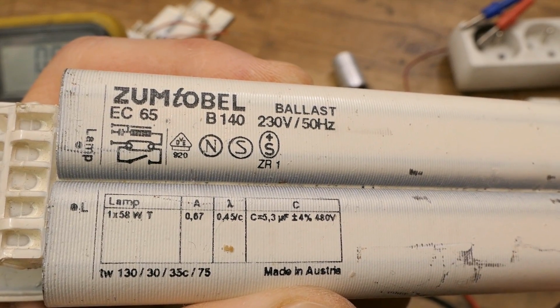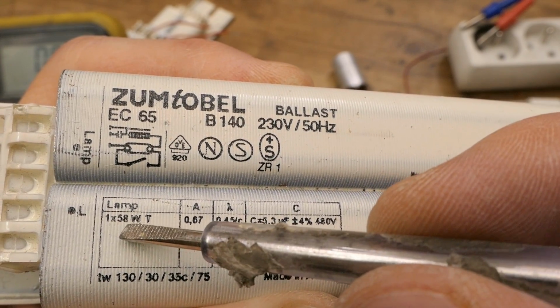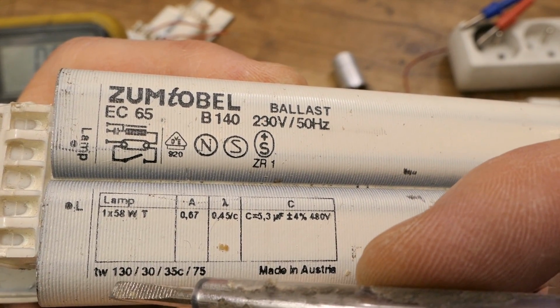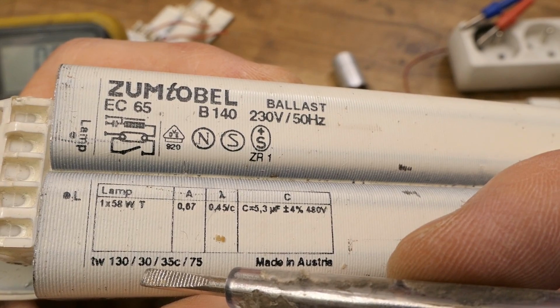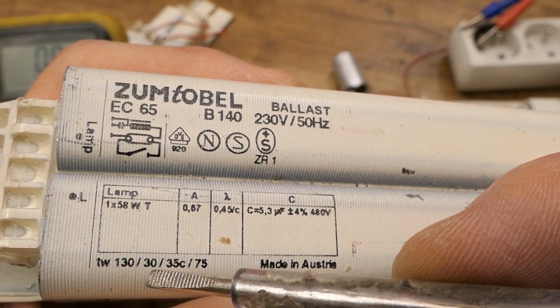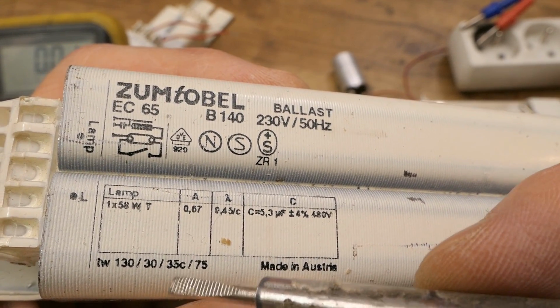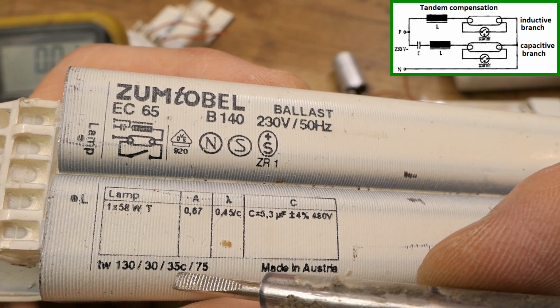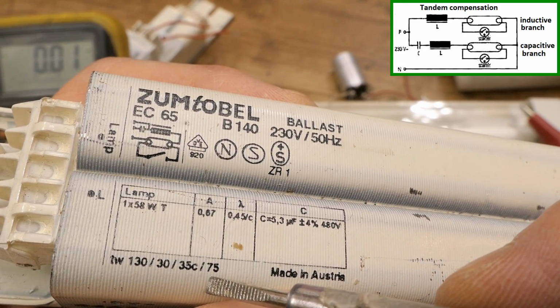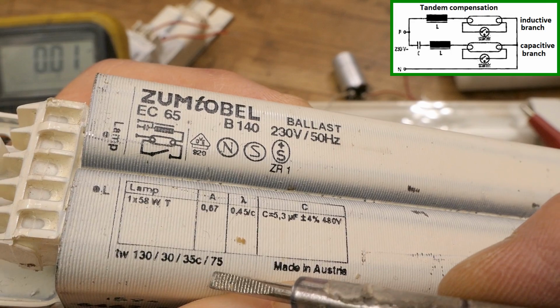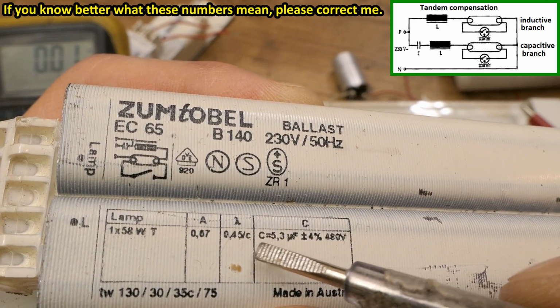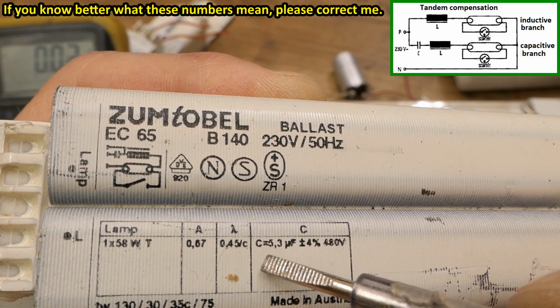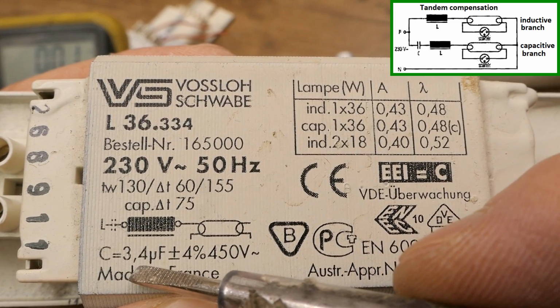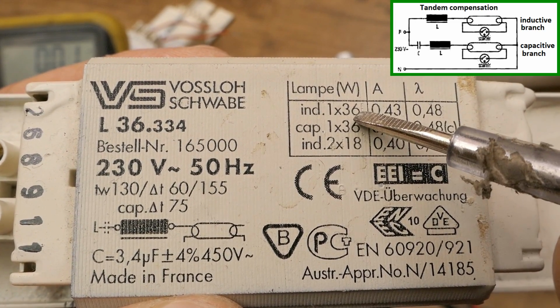To make it even more confusing, this is a 58 watt tube inductor, 130 degrees Celsius, 30 degrees Celsius temperature rise for normal operation, and 35 degrees Celsius temperature rise for the capacitive branch. And 75 degrees Celsius temperature rise is probably again the abnormal one, and the series compensation capacitor is 5.3 micro or 3.4 micro for a 36 watt tube.